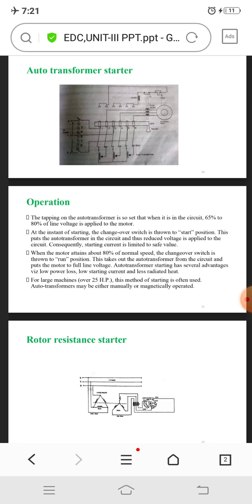Reduced voltage for starting can be obtained from three auto transformers connected in star. If the voltage is reduced to a fraction X of the rated voltage, the motor starting current is IST equal to X into ISC. The tapping on the auto transformer is so set that when it is in the circuit, 65% to 85% of the line voltage is applied to the motor.